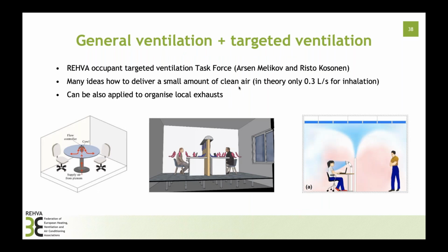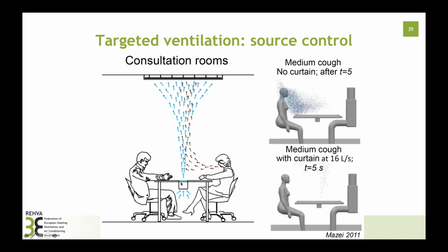When we come to targeted ventilation, this can be highly useful in small rooms when you need to separate two people or to make clean air zones. And this here is just a classical personal ventilation solution you can provide for a fixed seat, very clean air, and indeed very low concentration and so on. But also separation can have a big meaning. And remember that theoretically, human peak inhalation is only 0.3 liter per second, but typically we supply 10 liters per second. So efficiency in general ventilation is not too good, and that's one reason to go to personal ventilation. And sometimes these systems do not need to be too complicated. Even with a simple fan, you can make a separation, and numerical studies have shown it to have a lot of effect.